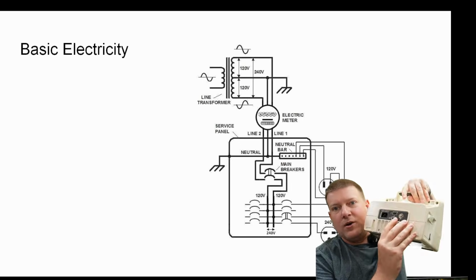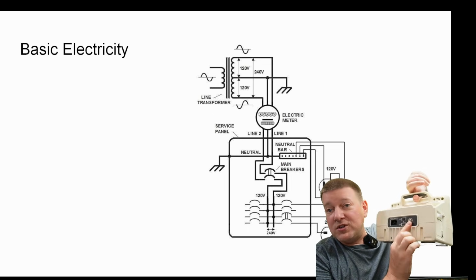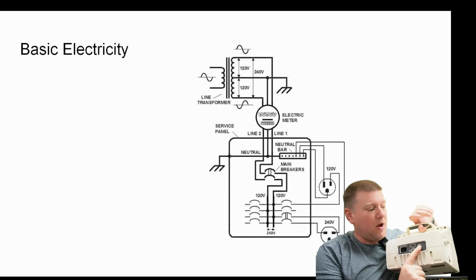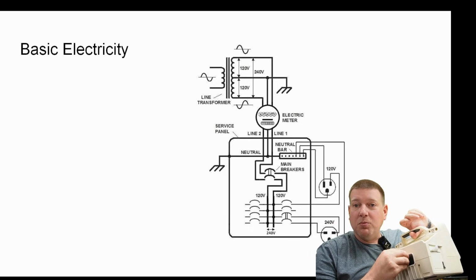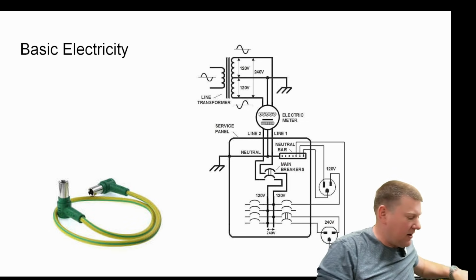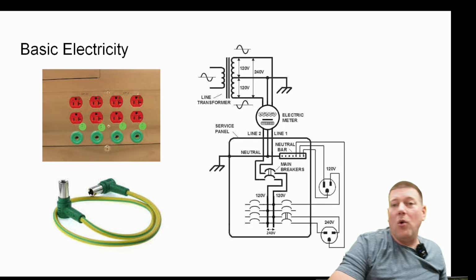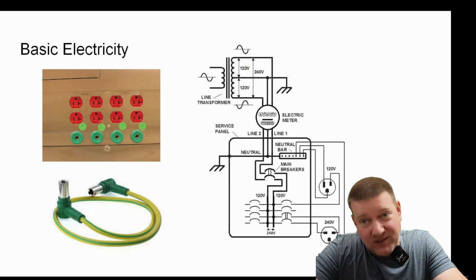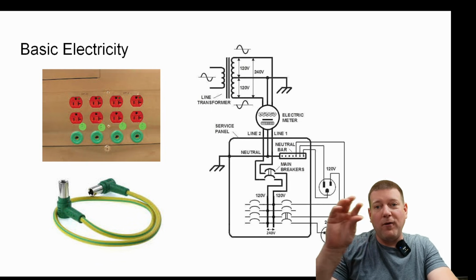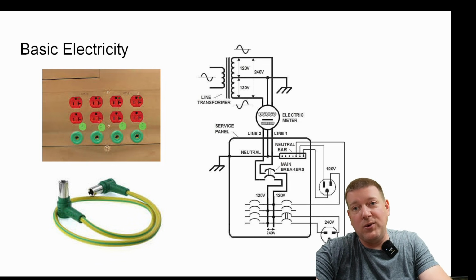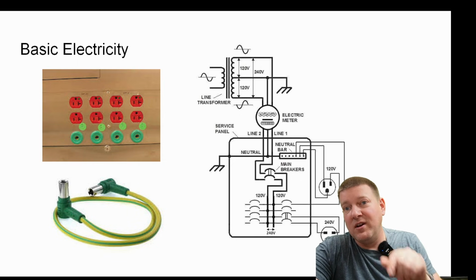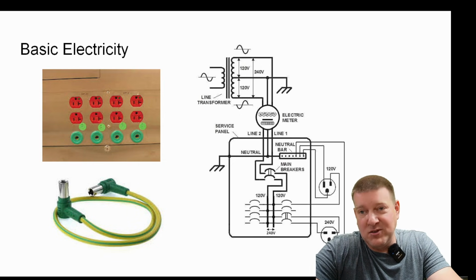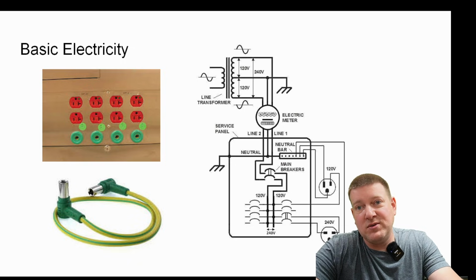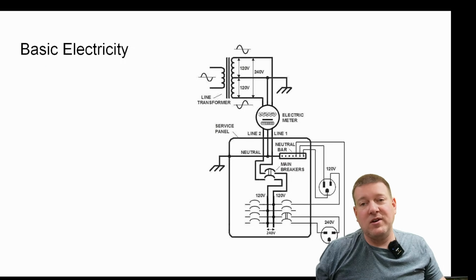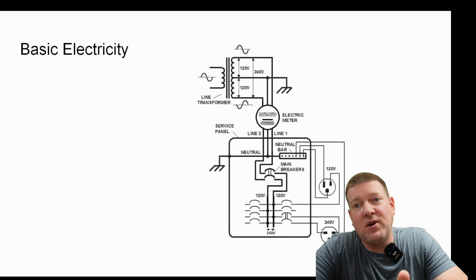And we have ground reference points like this one right here, which is also a redundant ground, because there are clips that you can put on there and they will connect to old school redundant ground panels. So you'll have a panel on the wall full of ground points where you have these large, almost like phonograph type plugs.